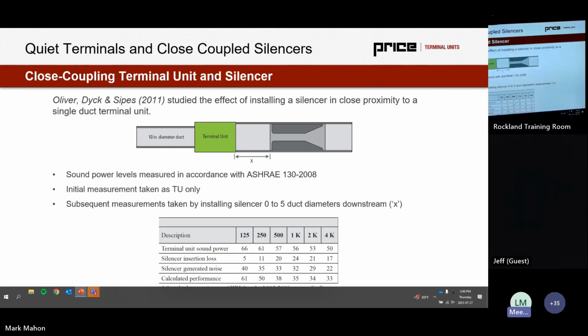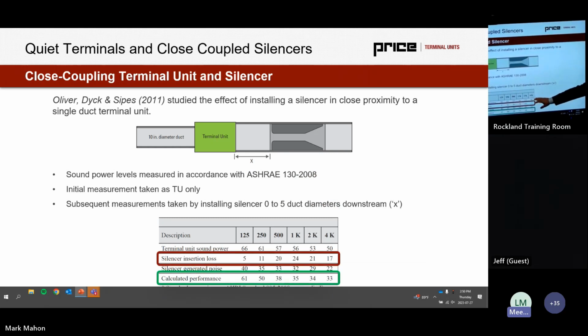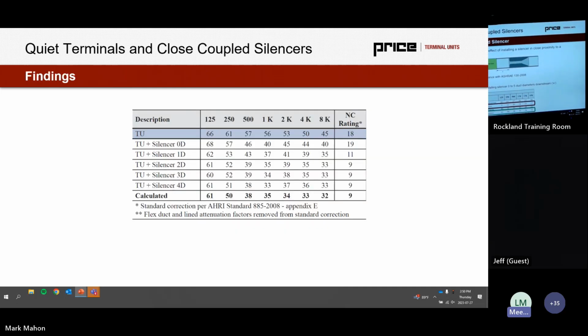And there's a good example of this that we actually researched and studied. So the thought process here is we can take our terminal unit sound power value, subtract the silencer insertion loss, and we should be able to calculate out the performance that we're actually going to achieve. However, we tested this in the lab at a close coupled condition, 1 duct diameter, 2 duct diameter, 3 duct diameter, all the way to 5 duct diameters, to quantify how much install condition actually influences the sound power value of the assembly. And the testing showed that a silencer can end up being a kazoo if you place it directly on the end of a terminal unit.